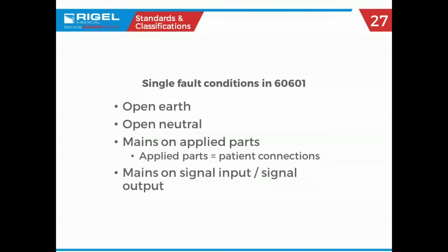For 60601, single fault conditions are numerous. Open ground, open neutral, reverse polarity. So, take your hot wire and white wire and flip them around. That isn't done often now in the States, because if you do open neutral and you do reverse polarity, you're also doing a power cycle to the piece of equipment, right? And now with more and more computers as part of the system, you gotta wait for that computer to boot up again. So here in the States, we typically don't do reverse voltage. In fact, some pieces of equipment can be damaged.